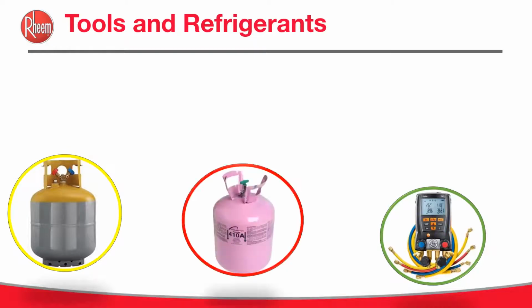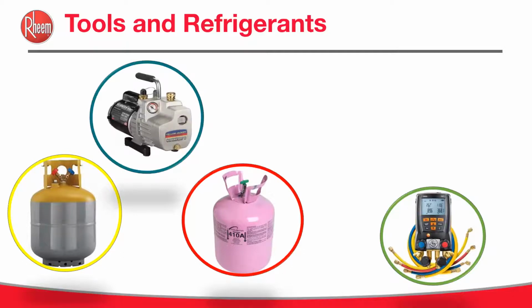Appropriate refrigerant as specified on the unit rating plate. At this time, we're using 410A, but this will change going forward. So we want to make sure that we know what refrigerant is in the system and we have the proper tools. Vacuum pump: a vacuum pump is used to remove moisture, air, and non-condensables from the refrigeration system.